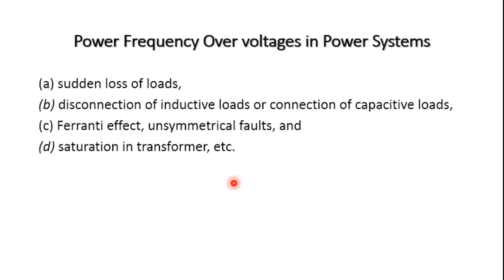These overvoltages, subjected to power frequency harmonics with frequency near the operating frequency, are going to occur during tap changing operations or due to magnetic or ferro-resonance phenomenon in large power transformers. This results in resonating overvoltages due to series capacitors with shunt reactors or transformers. The duration of these overvoltages may be from one to two cycles or sometimes a few seconds, depending upon the overvoltage protection employed.